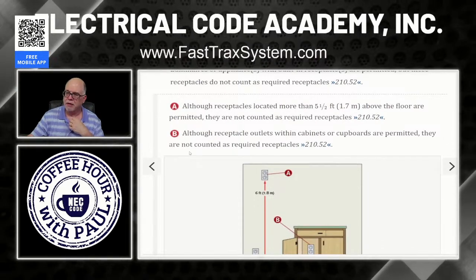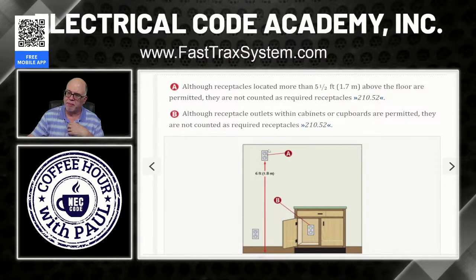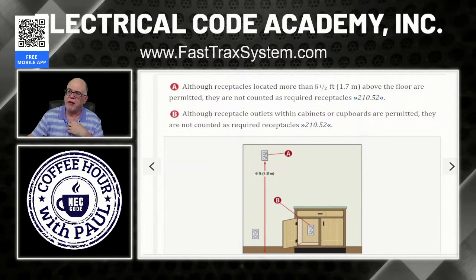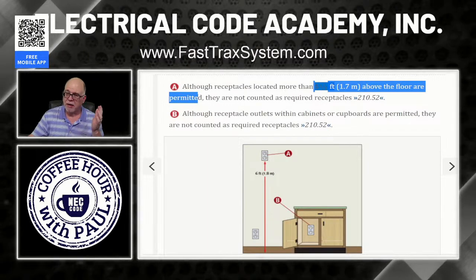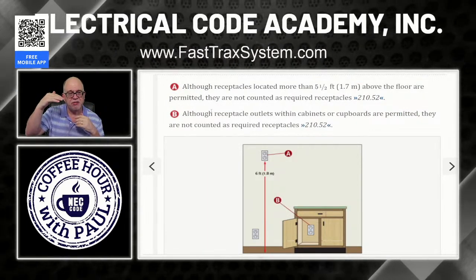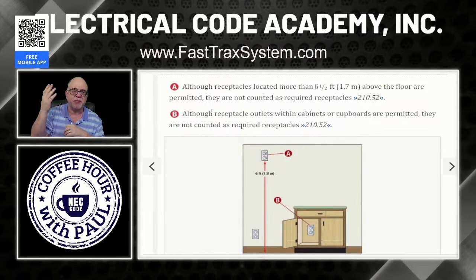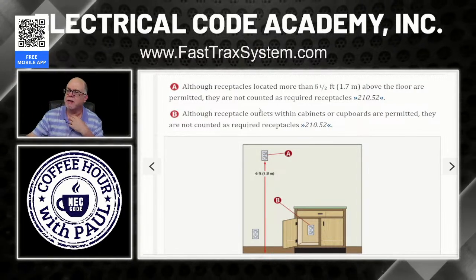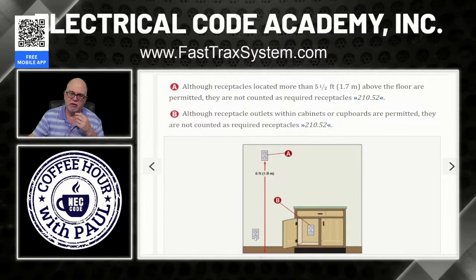Now, let's look at A. All right, so where is this one at? This one's at 6 feet right now. For some reason, they put this one up high. Maybe this is for a flat screen TV. Receptacles located more than 5.5 feet above the floor are permitted. And you could do that. I mean, you could put that receptacle above your cabinet, let's say in the kitchen, to do accent lighting. You can put a receptacle up high for something else, whatever you want. It still just can't meet the spacing requirement. It's an additional one. You put whatever you want, but you still got to maintain the spacing, right? So this is 6.5 feet, so that's not going to qualify. That's why you have this one down here, okay?